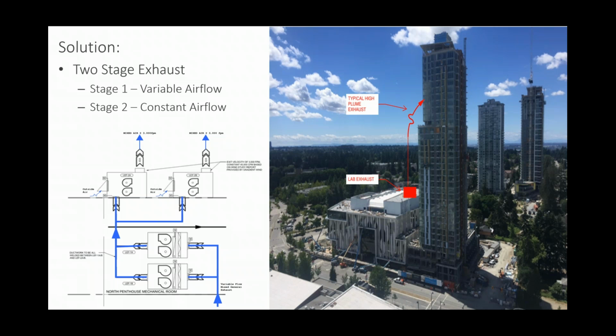And what we found was that having a lot slower moving air allowed it to disperse quicker, to the levels that we needed before it hit that high-rise building. The units up on the roof are constant volume for the reason of mixing outside air with that lab exhaust air. We've typically got about 50,000 CFM out of the labs, and those rooftop units are at about 90,000 CFM. So they're mixing clean air and diluting the air prior to exhausting it out of their stacks at about 3,000 feet per minute. And it was a lot of iterations trying to figure out exactly what the best solution for this was.